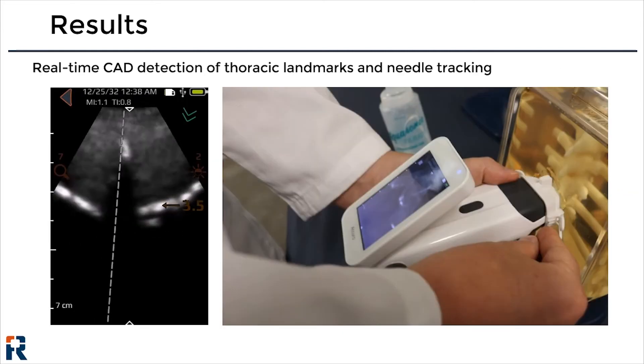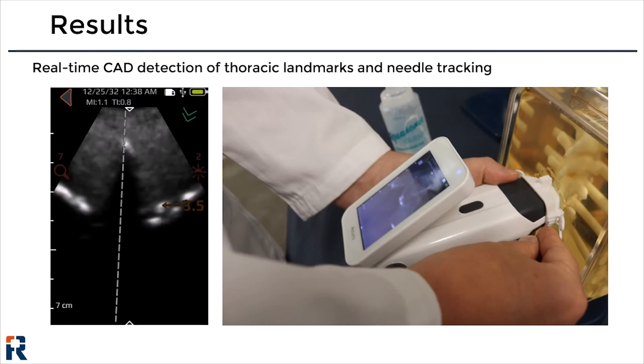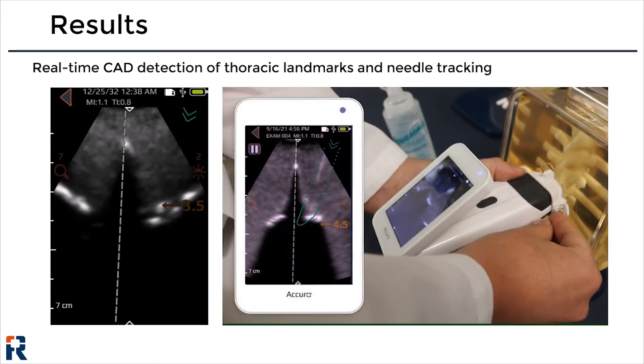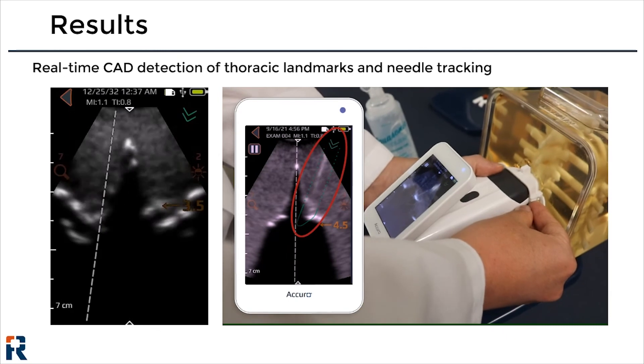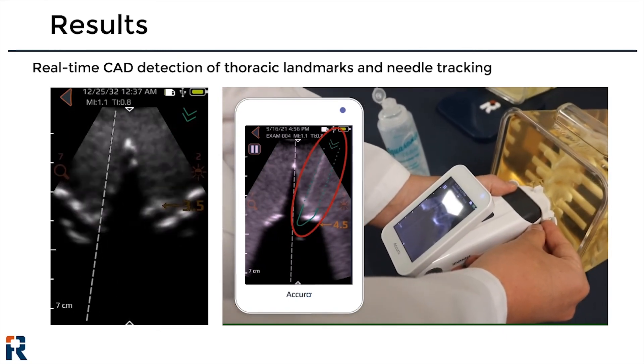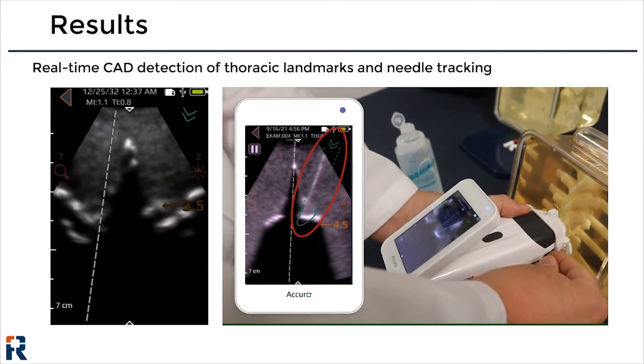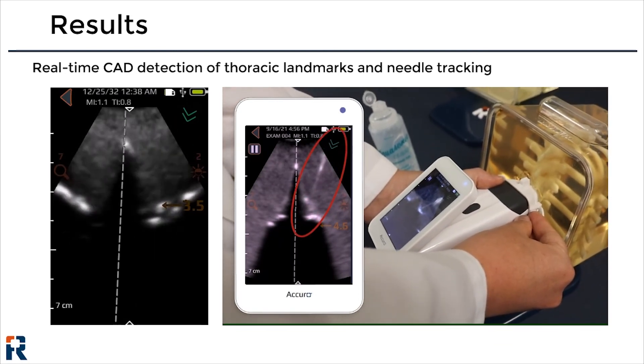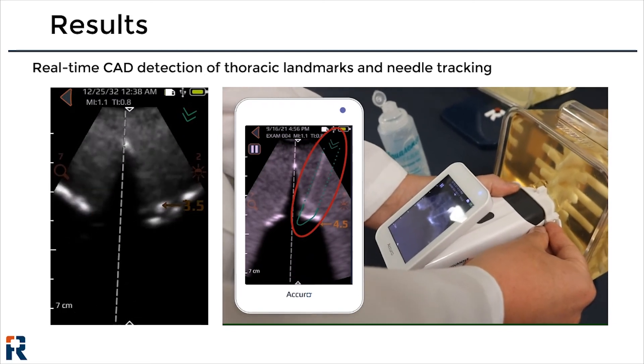The video on the left shows a short video capture of the real-time anatomical annotations provided by the computer-aided detection algorithm. The video on the right depicts a simulated needle placement procedure in a thoracic spine phantom, demonstrating how the imaging mode is intended to be used clinically. On the Accuro screen, you can see the needle following the green needle trajectory to the thoracic lamina. The angle of needle insertion is enforced by the white Accuro locator that clips onto the front of the ultrasound probe.